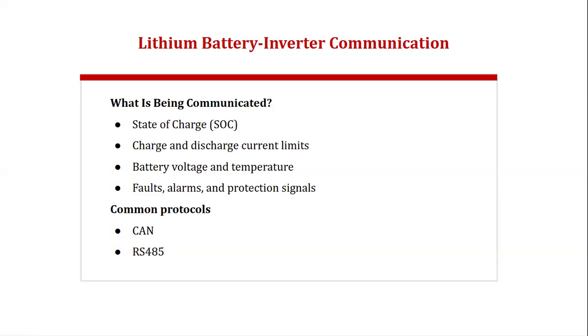And then they communicate the battery status, state of charge, SOC. You know, is the battery fully charged? You can see what the percentage of the battery is on the inverter if proper communication is established. It's not the battery telling you that I am 10% and the inverter telling you that the battery is 200%. You'll not be wondering, why am I seeing these low bars? No. If proper communication is established, whatever you are seeing on the screen of the lithium batteries, you also see on the inverter in terms of SOC percentage and all.